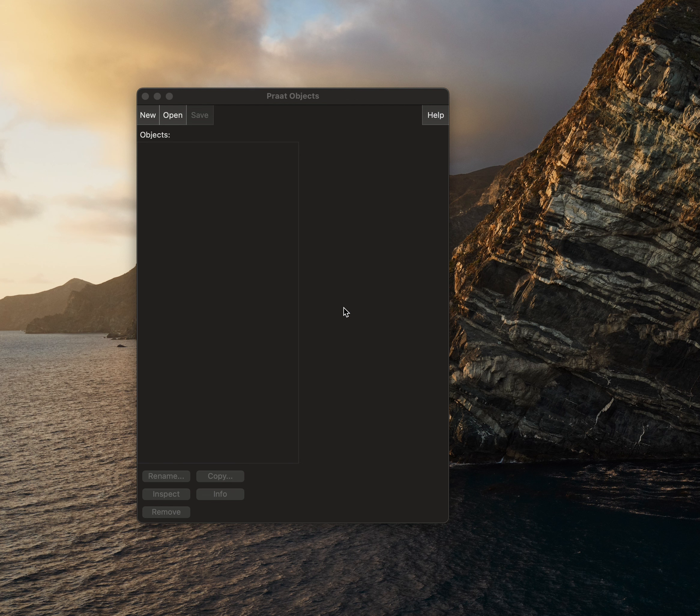This will involve a few different steps. The first will be to make sure that the softest phonation is detectable on our microphone and sound source. The second step will be to ensure that the loudest phonation is being detected and not being clipped off by our microphone and sound source. And then lastly we'll need to calibrate our sound intensity level readings.